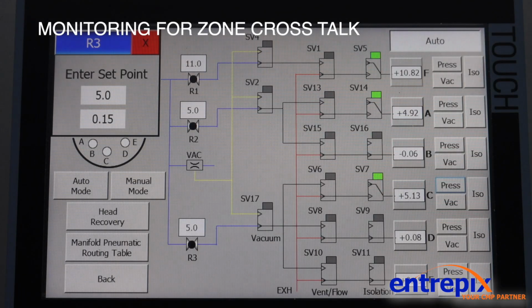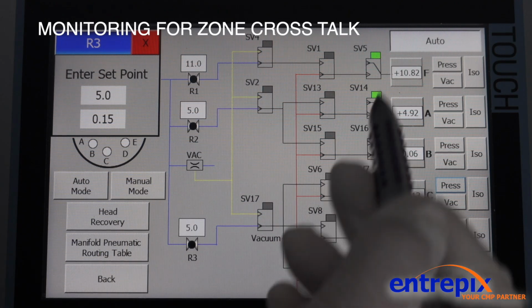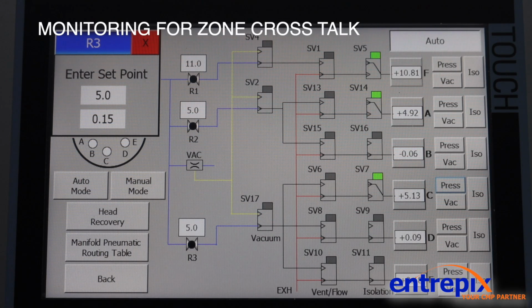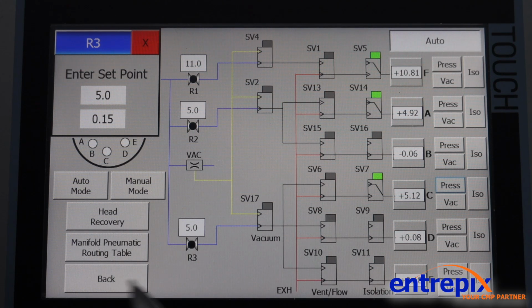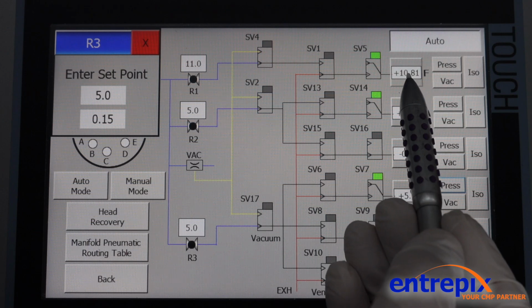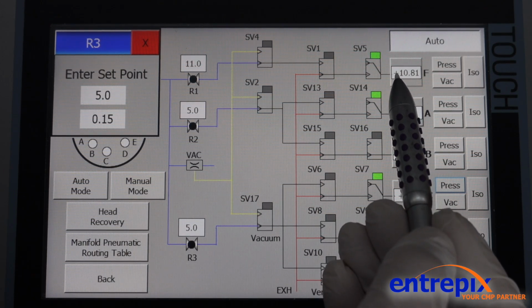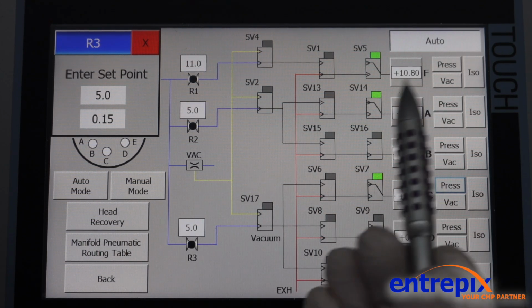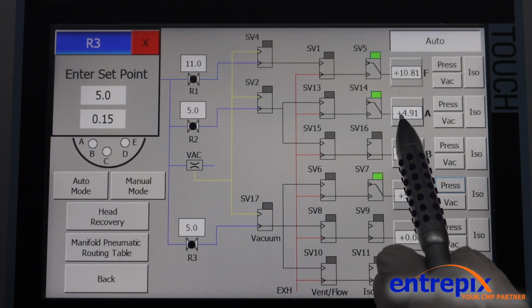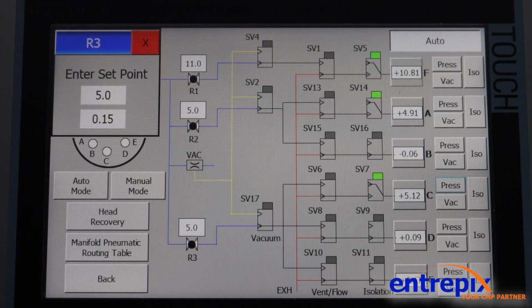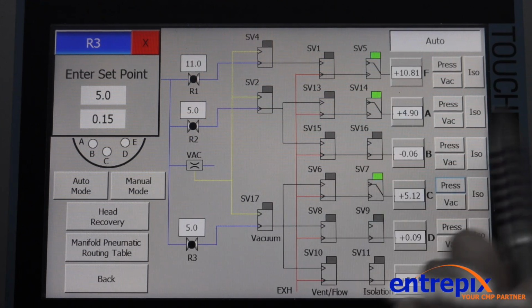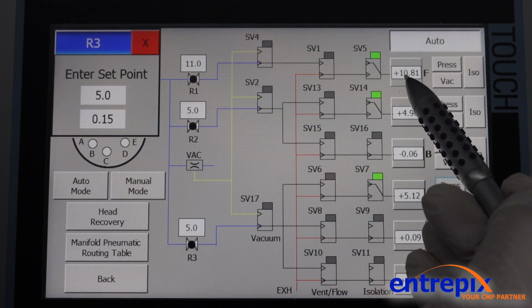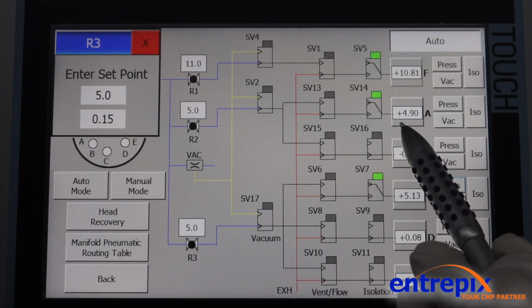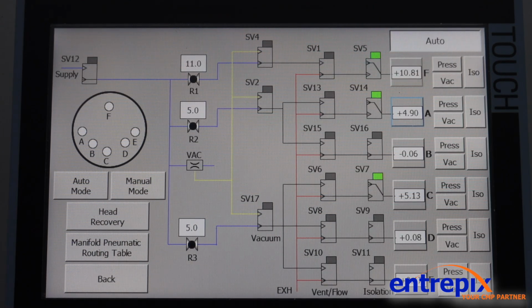So now we're just monitoring for a leak on all those zones over whatever duration we decide is appropriate. We're also checking for some crosstalk, because if you notice here, the retaining ring zone is set at approximately 10.8 psi, and our membrane is at 4.90. If there was a leak between these zones, you would see that the retaining ring would be losing pressure and the membrane would be gaining. Since we're not seeing that, we know that there's no crosstalk.